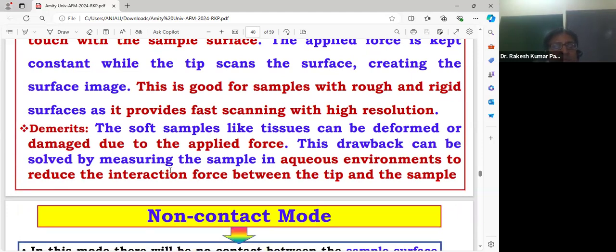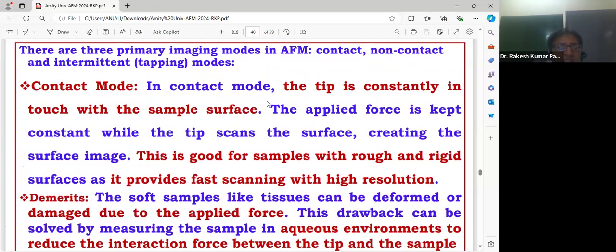But what are the demerits of this mode? Soft samples like tissues can be deformed or damaged due to this applied force. This drawback can be overcome by measuring the sample in an aqueous environment. Suppose there is a biological sample, and there is no facility of AFM in other modes like non-contact mode. How can we overcome it? The AFM can be used in aqueous environment mode. It will reduce the interaction force between the tip and the sample. So what will happen? It will prevent damage to the sample. So each mode has its own merits and demerits. So this is about contact mode.